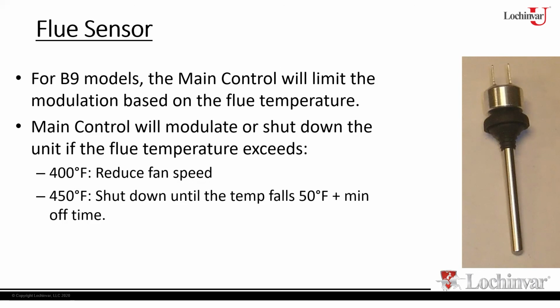Now, when it shuts off, it's not going to shut off on a lockout. It's going to go into what's called a blocking condition. It's going to say blocked high flue temperature. So what that means is if you still have a call for heat going, if that flue temperature drops 50 degrees and a 1-minute timer has expired, then it's going to say, okay, we can go ahead and fire back up. So again, it's not a lockout. It's just a blocking that says, hey, something's wrong here. We're going to hold up for a moment.